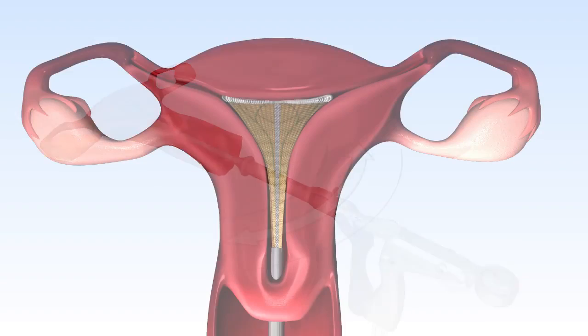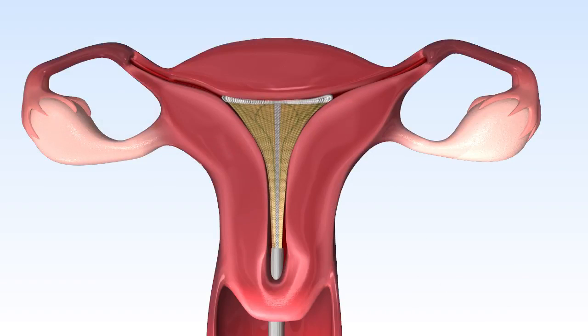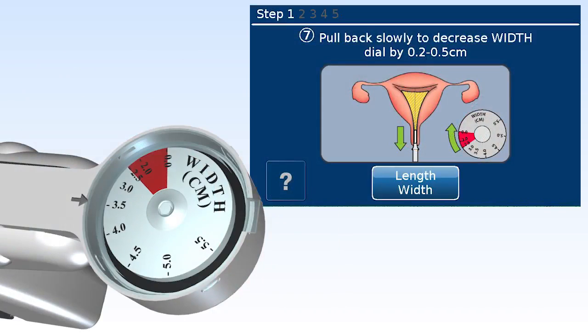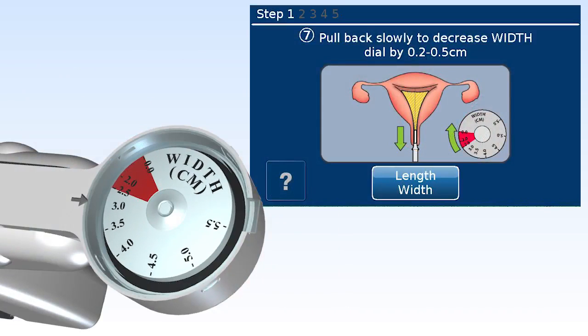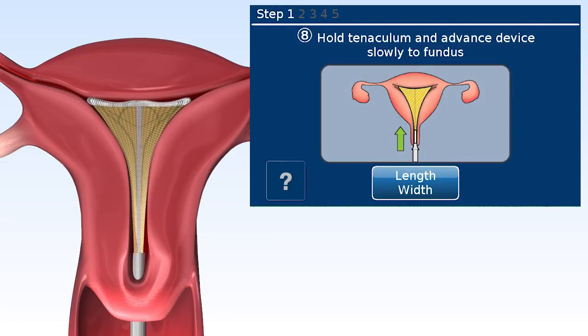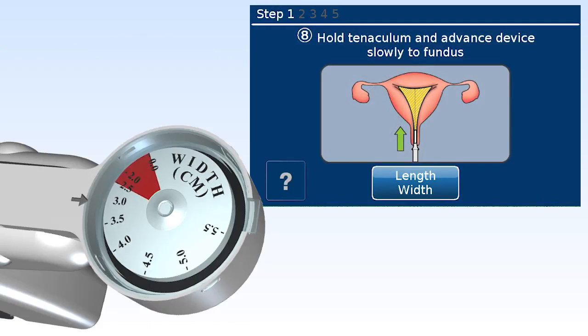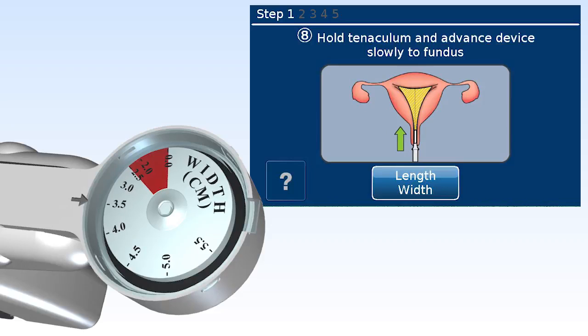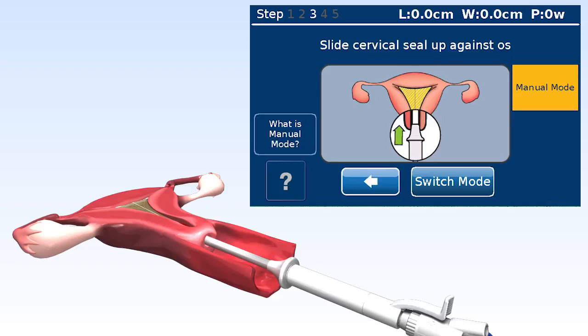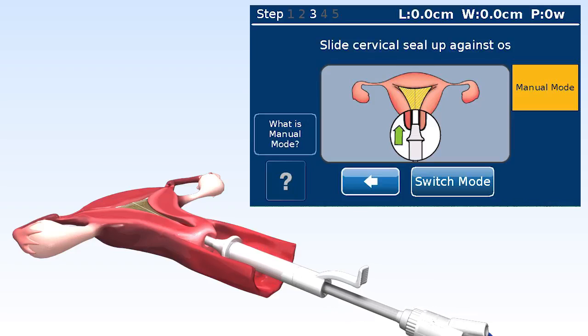To complete placement, slightly pull back on the device away from the fundus until the width dial reading reduces 0.2 to 0.5 centimeters. Advance the device slowly and gently to the fundus. The width should read greater than or equal to the previous measurement. Slide the cervical collar against the external cervical os using gentle pressure on the thumb tab. Keep the collar in this position for the rest of the procedure.